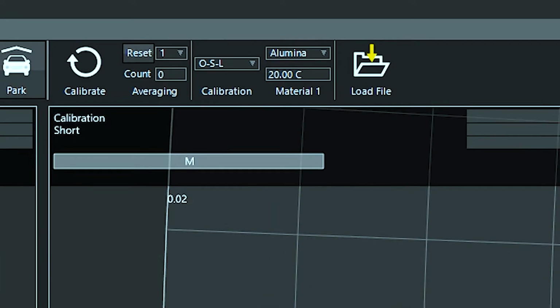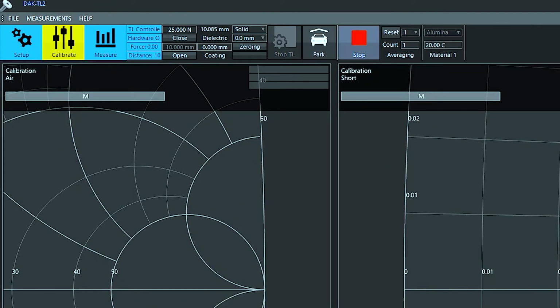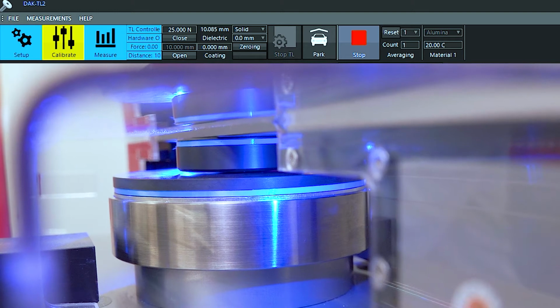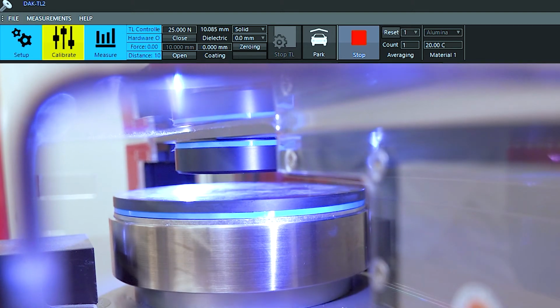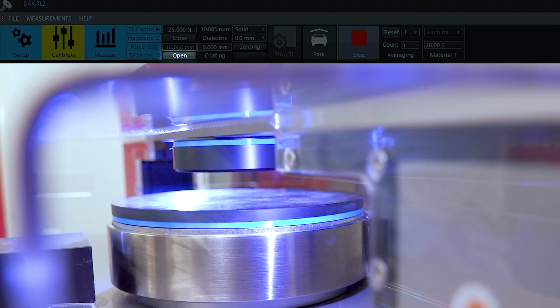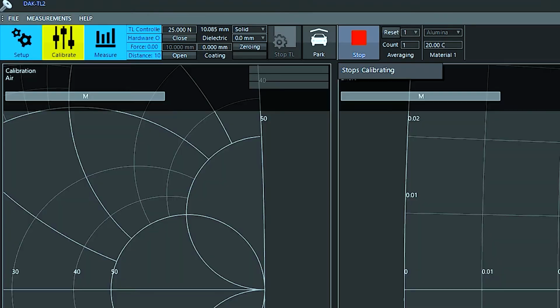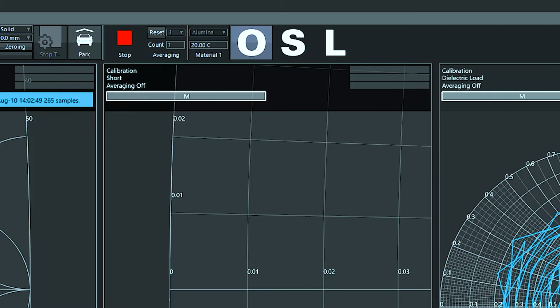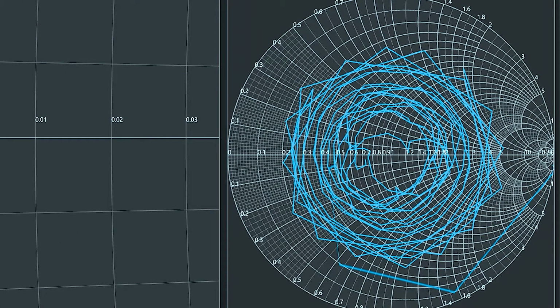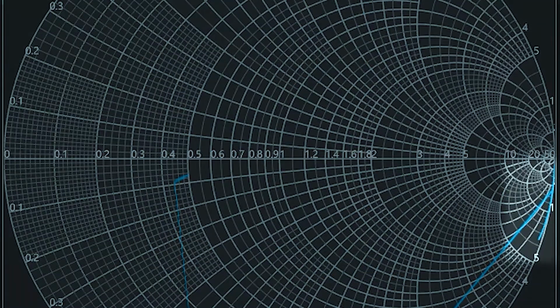Step 3. I start the calibration procedure by pressing the Calibrate button. Step 4. I make sure that the stage is fully open by pressing the Open button in the base system controller. Step 5. When the platform stops moving, I click on the O calibration button in the GUI. An ideal open circuit is the rightmost point of the Smith chart.